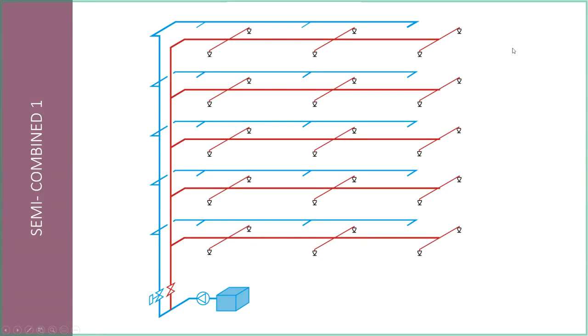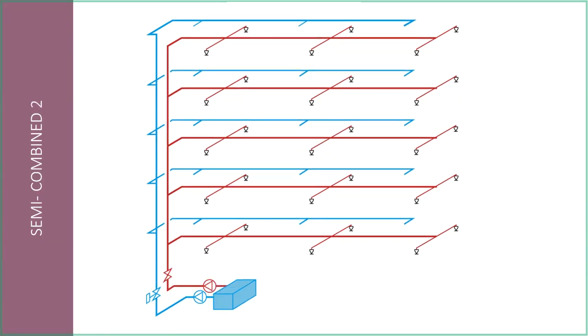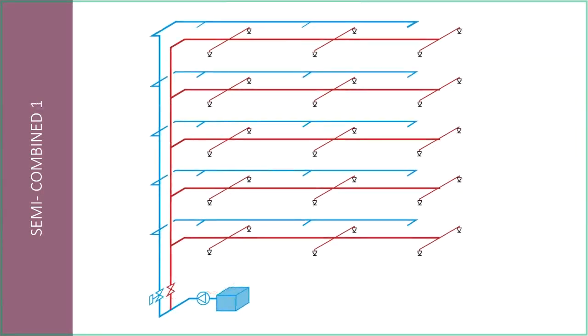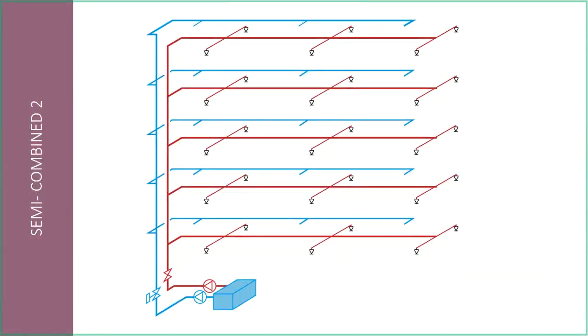This one here is a semi-combined system, so we are looking at a shared tank and a shared pump, and we have a separate riser. This one is the same, but we have a different pump. So you can see that of the two there, we've got one tank and one pump, and one tank and two pumps where you have a separate sprinkler pump. Again, those are two different ways of doing it.